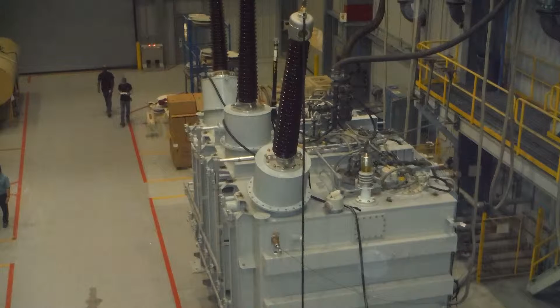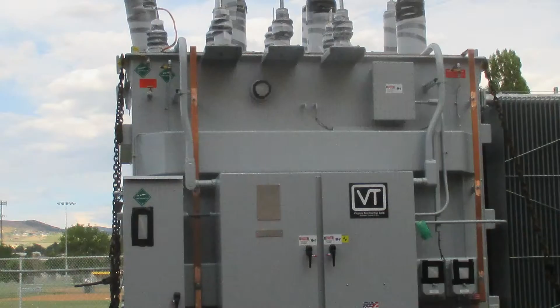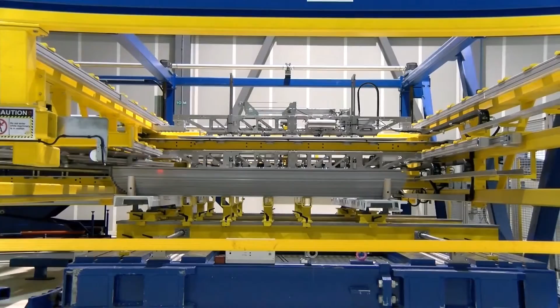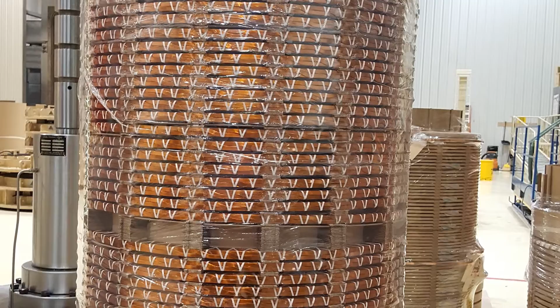A large power transformer, or LPT, is a large custom-built transformer that's a critical component of the bulk transmission grid. Because LPTs are very expensive and tailored to customers' specifications, they are usually neither interchangeable with each other nor produced for extensive spare inventories. Although LPTs come in a wide variety of sizes and configurations, they consist of two main active parts: the core, which is made of high permeability grain-oriented silicon electrical steel, layered in pieces, and windings, which are made of copper conductors wound around the core, providing electrical input and output.